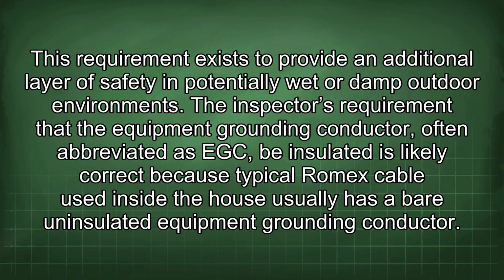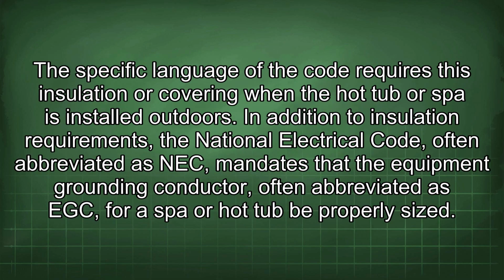The inspector's requirement that the equipment grounding conductor, often abbreviated as EGC, be insulated is likely correct because typical Romex cable used inside the house usually has a bare, uninsulated equipment grounding conductor. The specific language of the code requires this insulation or covering when a hot tub or spa is installed outdoors.